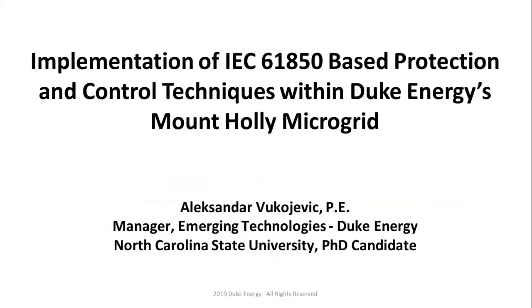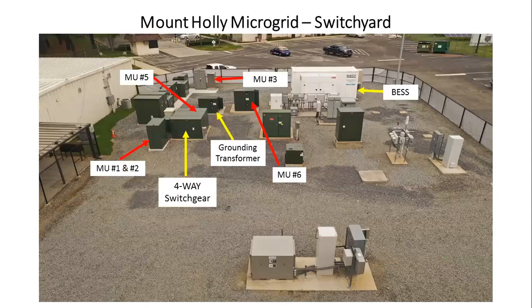Now, everything that you have seen in the microgrid was done typically using DNP3 and Modbus protocol. I have done the design of all the protection and control and all the high voltage stuff, but we have also done a lot of wiring in the yard. So what we try to do is, can we actually use IEC 61850 and some kind of control techniques to protect this microgrid, right? Why? Because that simplifies wiring, reduces the cost of implementation, et cetera. So I'm going to show you now how everything looks.